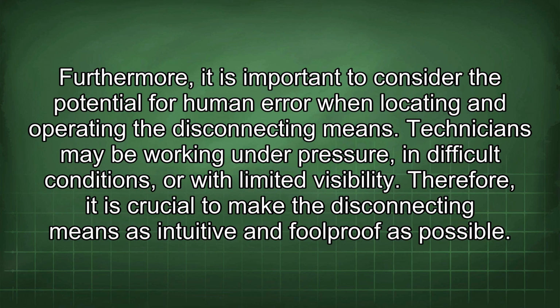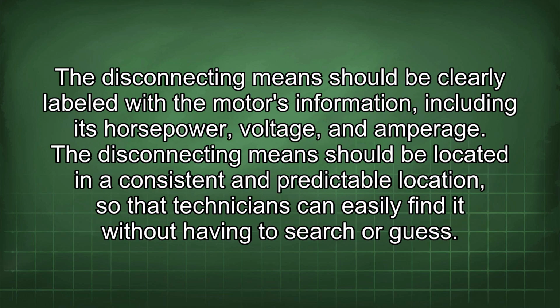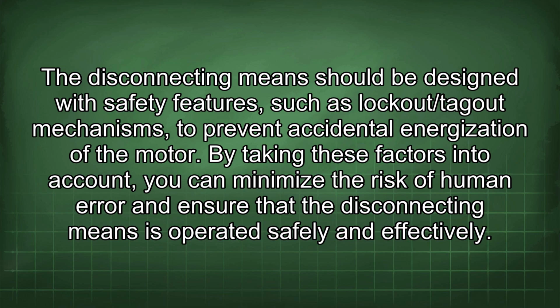Furthermore, it is important to consider the potential for human error when locating and operating the disconnecting means. Technicians may be working under pressure, in difficult conditions, or with limited visibility. Therefore, it is crucial to make the disconnecting means as intuitive and foolproof as possible. The disconnecting means should be clearly labeled with the motor's information, including its horsepower, voltage, and amperage. The disconnecting means should be located in a consistent and predictable location, so that technicians can easily find it without having to search or guess. The disconnecting means should be designed with safety features such as lockout/tagout mechanisms to prevent accidental energization of the motor. By taking these factors into account, you can minimize the risk of human error and ensure that the disconnecting means is operated safely and effectively.